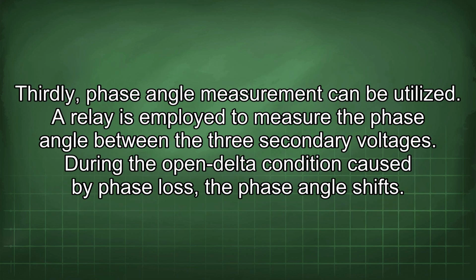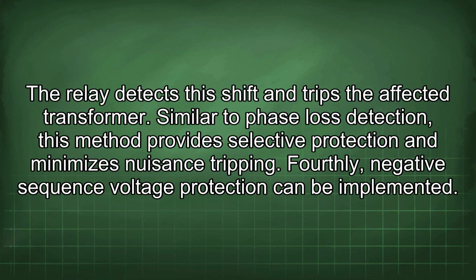Thirdly, phase angle measurement can be utilized. A relay is employed to measure the phase angle between the three secondary voltages. During the open delta condition caused by phase loss, the phase angle shifts. The relay detects the shift and trips the affected transformer. Similar to phase loss detection, this method provides selective protection and minimizes nuisance tripping.